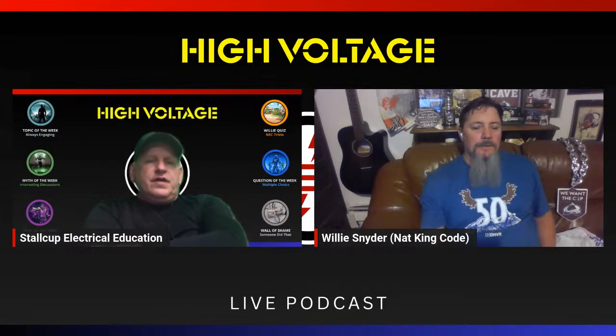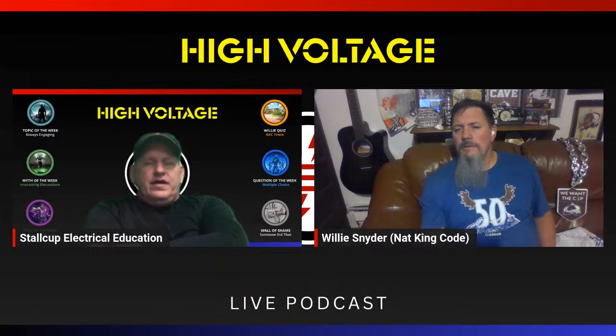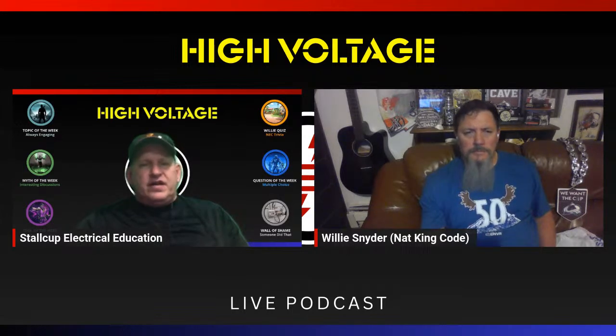For sure. And another thing I want to say, just to finish that up, is when you're looking at that, you had two options. You either protected the load or the conductor, and your equipment grounding conductor was based on that. That's why 240.4(B) is that way. Now, if I was over 800 amps, the ampacity of the conductors has to exceed the overcurrent protection device rating. So you would drop down on anything over 800 amps, but up to 800 amps, you're protecting that load or conductor. Just that alone ends the conversation.